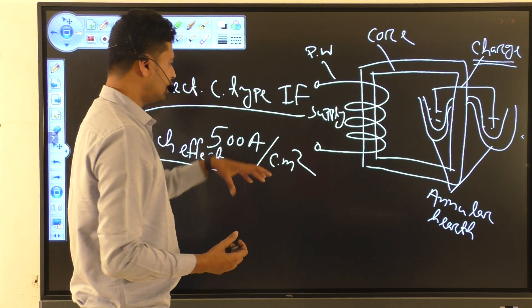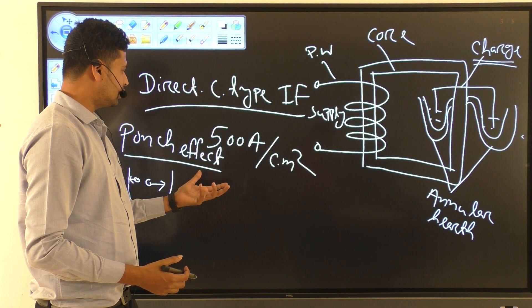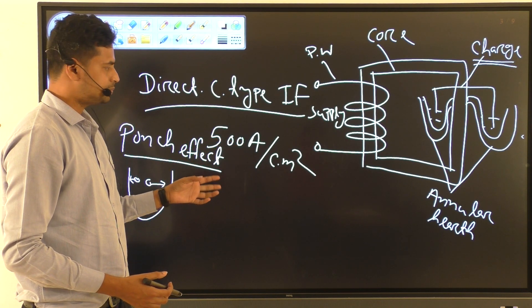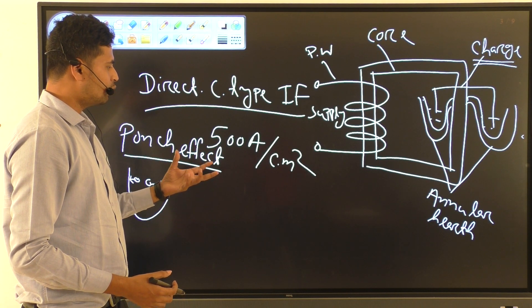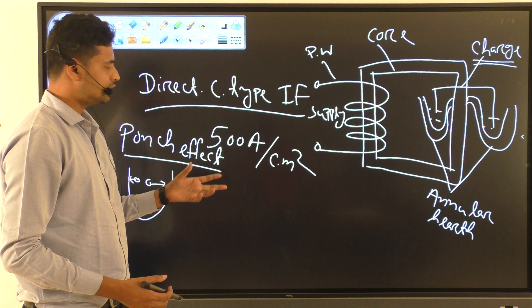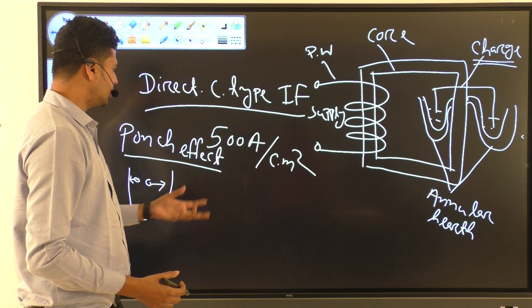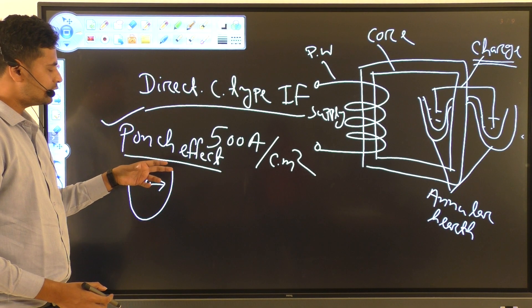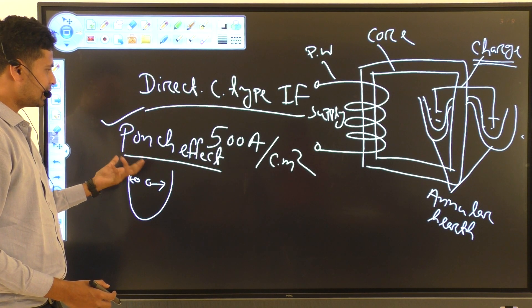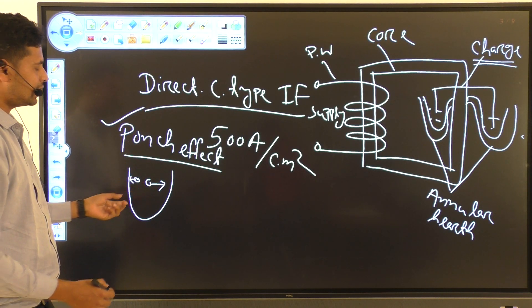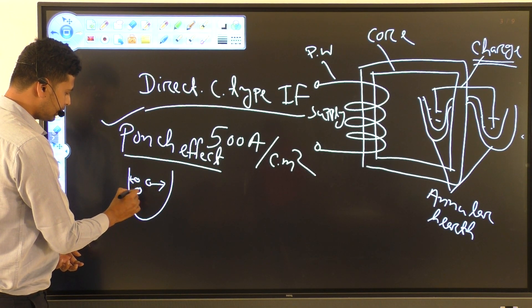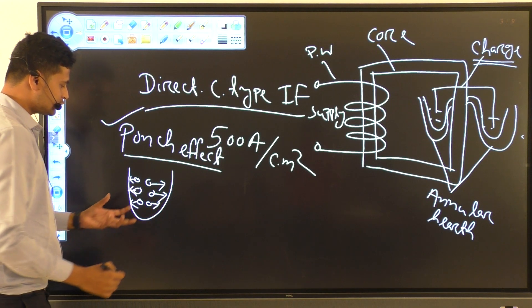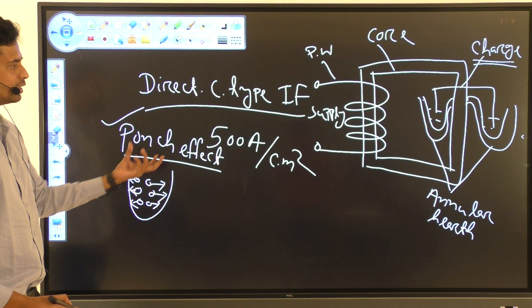The second demerit is that it cannot be operated at high frequency. If the current density is raised to around 500 amperes per centimeter square, it produces more reactance and the operation fails. This produces what is called the pinch effect. Due to high frequency and high reactance, the charges in the annular hearth are repelled from each other, and there is a risk of overflow of the molten metal from the annular hearth.